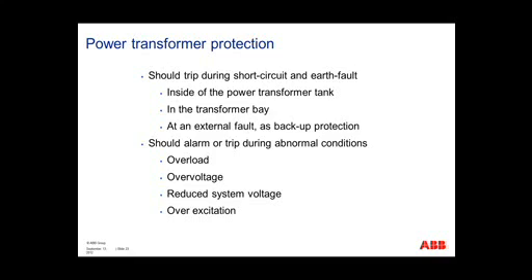Your power transformer protection should trip during short circuit and earth fault, and this should be an instantaneous trip inside of the power transformer bank. It should also be an instantaneous trip in the transformer bay. You should also have protection for external faults as a backup protection if your primary protection did not clear the fault fast enough. The first part is going to be your instantaneous stuff, and the bottom part is going to be the conditions that are time-based. So you should not trip immediately, but trip after if the condition continues on time, such as a continuous overloading condition or overvoltage, reduced system voltage, or overexcitation. And these should be alarmed as well, so action can be taken in the immediate steps, but not necessarily tripping out the bank.